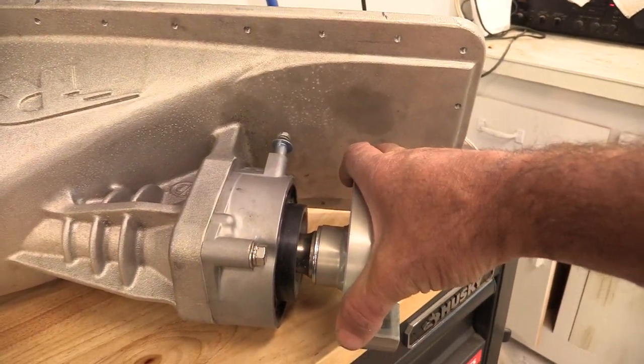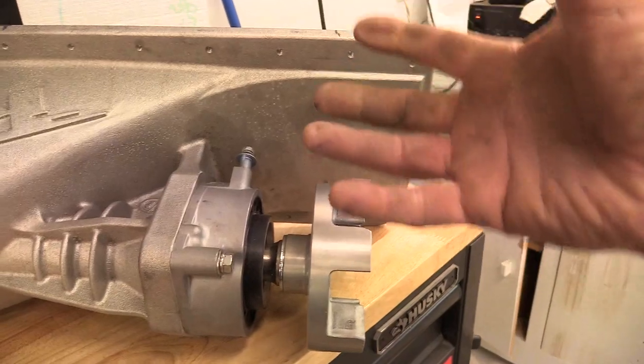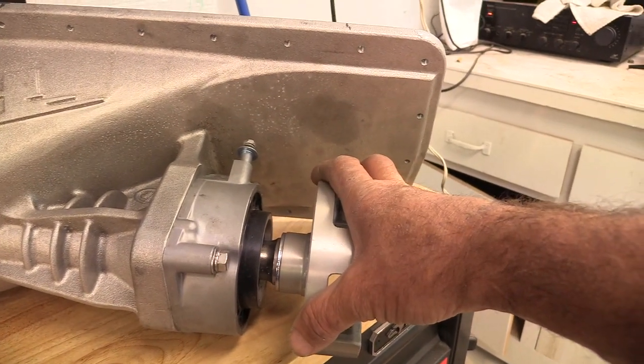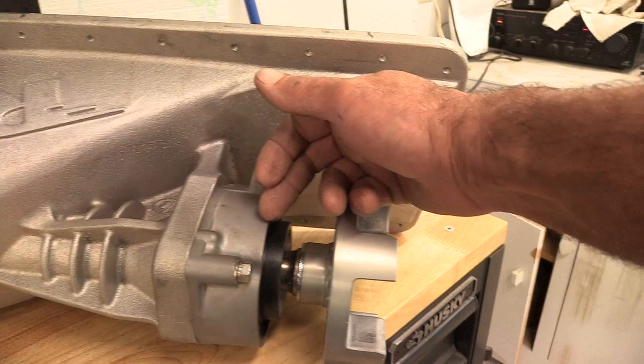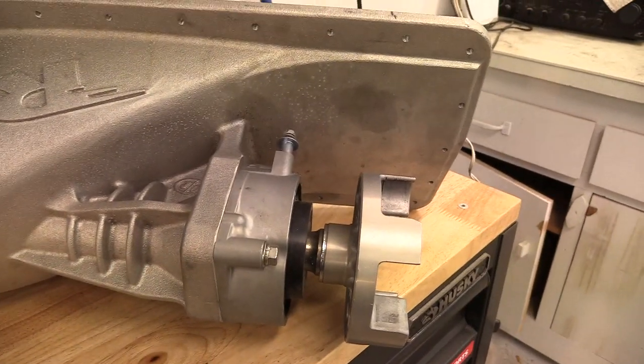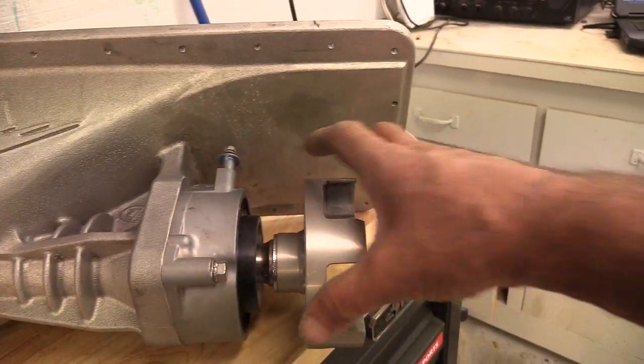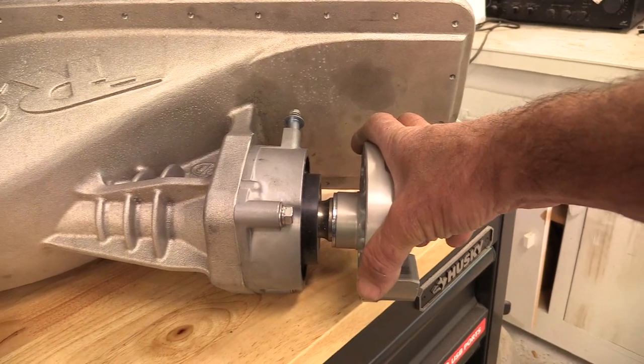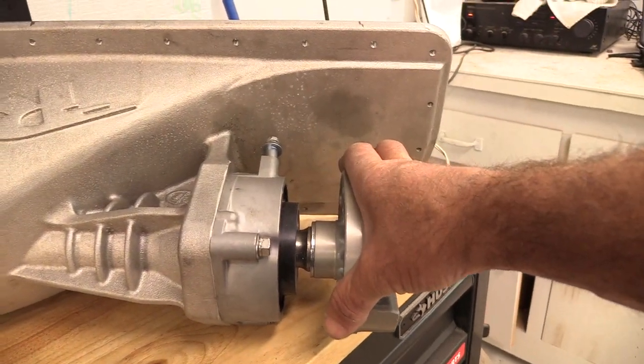Regardless, because there is some movement there — it's not much, but there is some. Most bearing housings I deal with, like housing with bearings on both sides and seals on both sides — I've dealt with those before in water pumps, recirculating pumps, things like that. There's a bearing carrier with two bearings and no up-and-down movement. But this is a different style. There may just be one bearing in there. It may carry a little bit of movement on purpose for motor torsion or whatever. If it's mounted right and centered, the motor's torque wouldn't necessarily pull it off center, or at least not enough to have much of an effect.